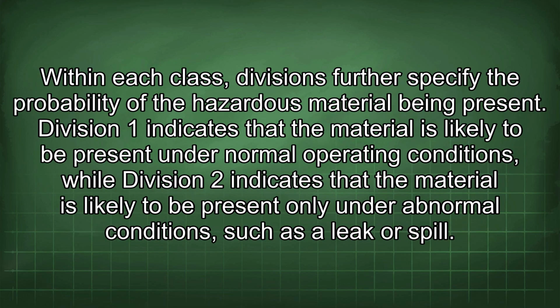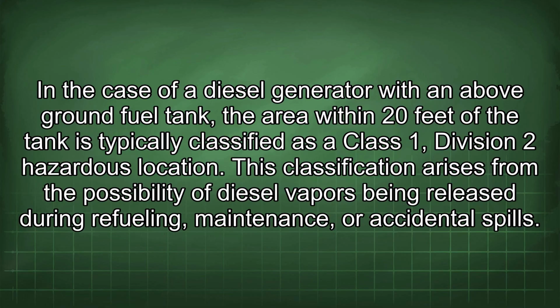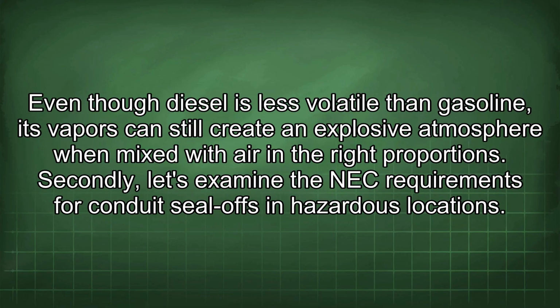Within each class, divisions further specify the probability of the hazardous material being present. Division 1 indicates that the material is likely to be present under normal operating conditions, while Division 2 indicates that the material is likely to be present only under abnormal conditions, such as a leak or spill. In the case of a diesel generator with an above-ground fuel tank, the area within 20 feet of the tank is typically classified as a Class 1, Division 2 hazardous location. This classification arises from the possibility of diesel vapors being released during refueling, maintenance, or accidental spills.